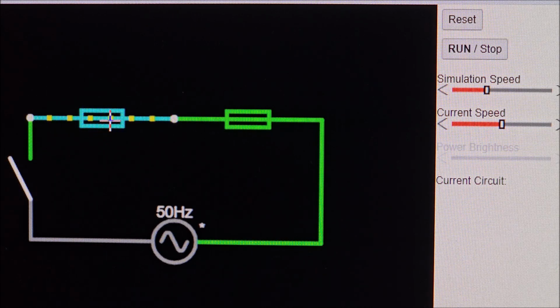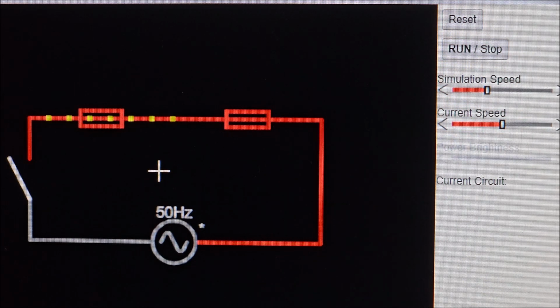These are the two RCDs, one inside the house and one outside. Although this one is a lower value, 10 milliamps, we are actually tripping the 30 milliamp one first. I expect this happens because it has a faster reaction time, and we're testing with a current enough to trip it. If the current were lower, this one should trip instead since it's the only one left that could react. Let's continue and see if I'm right.